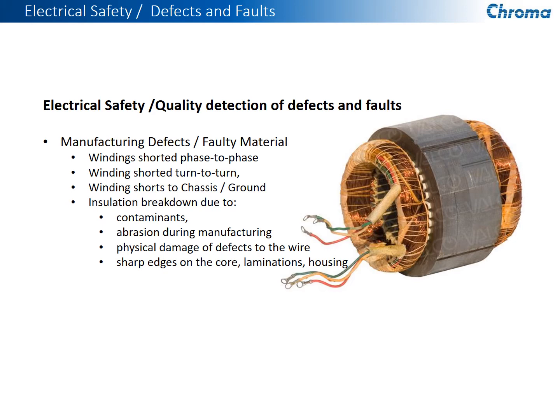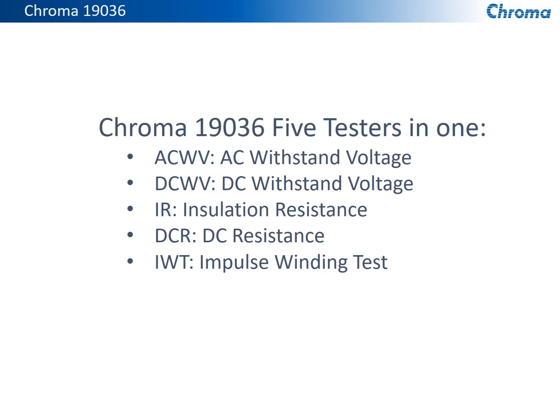So testing is critical. So Chroma created the 19036 to do just that, to do multiple tests, because not one test by itself can do a complete job of determining a fault within those types of devices. So it includes things like AC withstand voltage, DC withstand voltage, or both of these are also referred to as high pot tests, insulation resistance testing, DC resistance measurements of the windings themselves, and impulse winding tests. So by combining all of these in one tester, it gives you one way to do a complete test on all of your devices, such as wire wound devices for transformers, motors, and inductors.